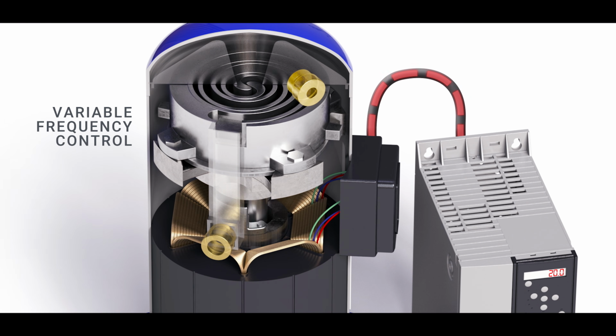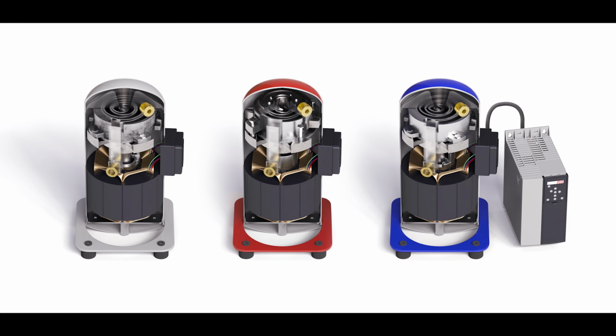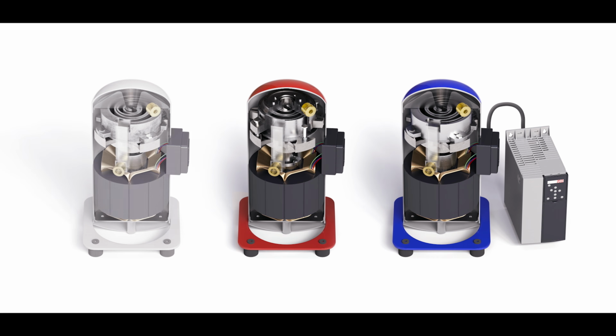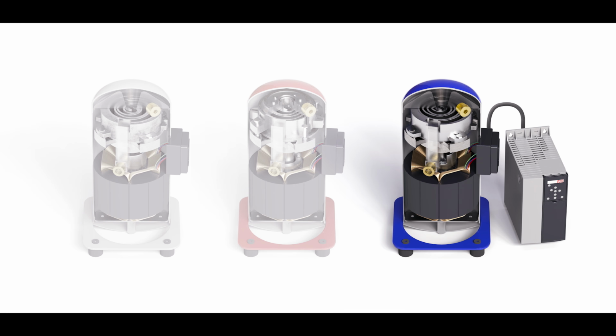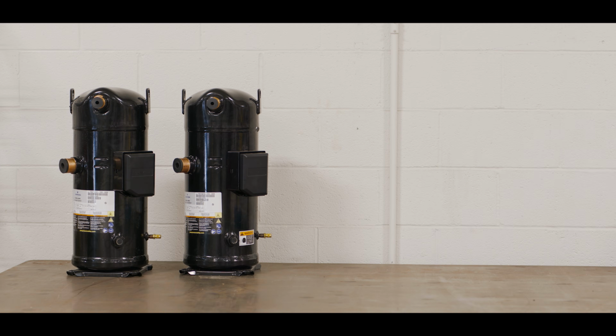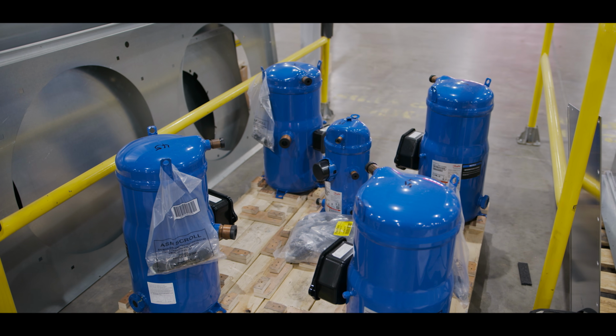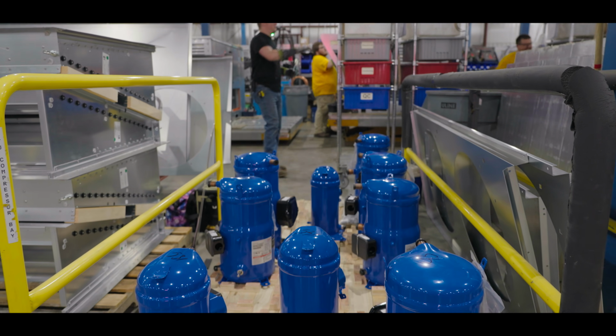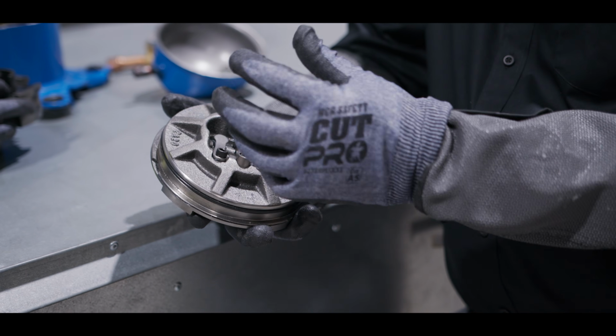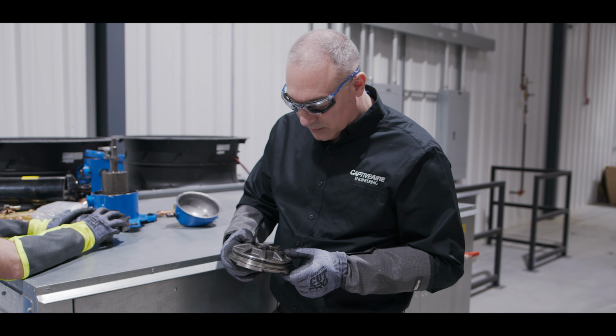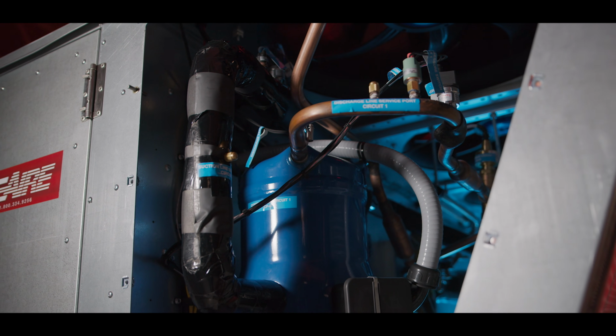So with that in mind, we were looking for the highest efficiency components, right? So on-off compressors were out. Digital compressors were out. At the time, there were really only two manufacturers that developed or had a design that could be scaled of variable scroll compressors that we could use. There are different levels of quality suppliers out there, but there's only one best component that we can use. And it's our job to ensure that we're selecting the best quality components for our end users.